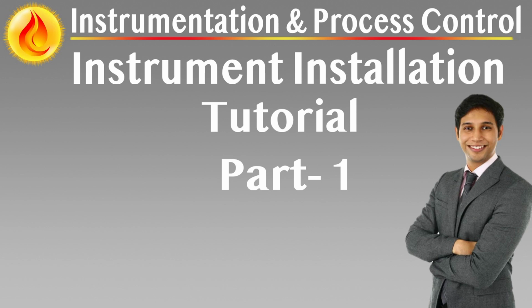Conclusion: diagnostic integration and plant lifecycle readiness. All installations must be traceable, reproducible, and diagnostic capable. Whether direct or remote mounted, the system must facilitate lifecycle management, including in situ testing, purge assurance, and density drift compensation. Every design decision must reflect the overarching priorities of measurement precision, personnel safety, maintenance accessibility, and robust compliance with industry best practices. Instrument process connections, foundation for accurate measurement and safe maintenance.